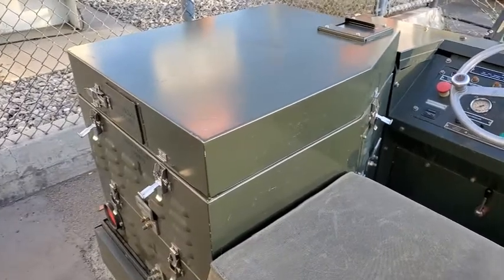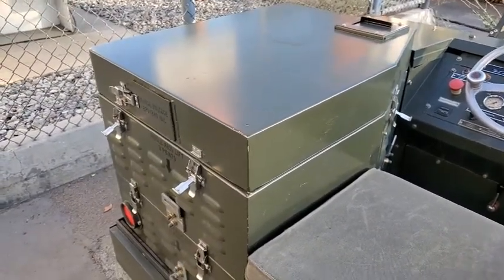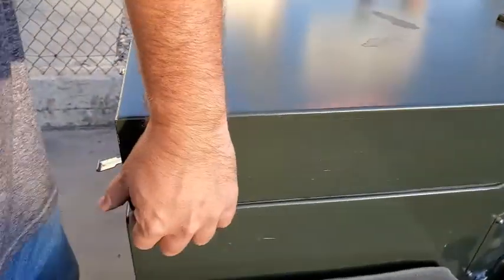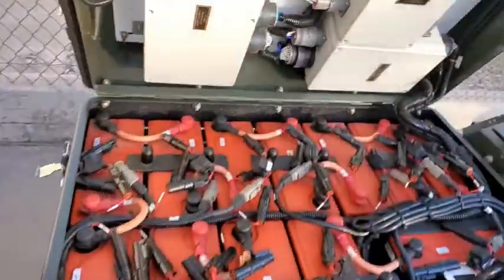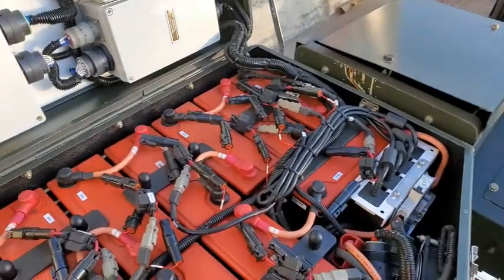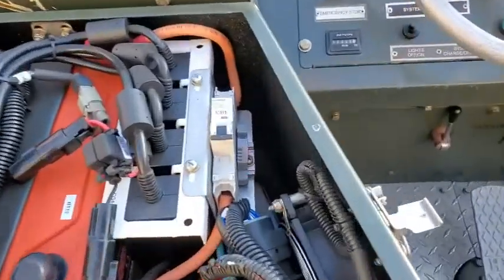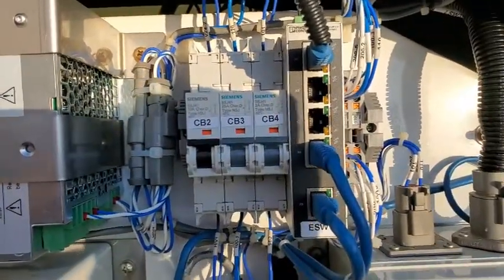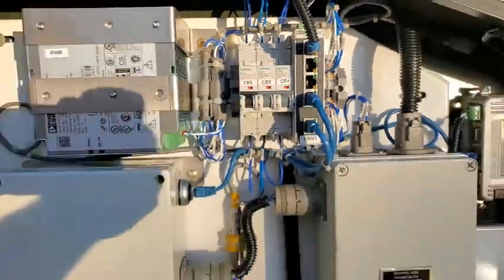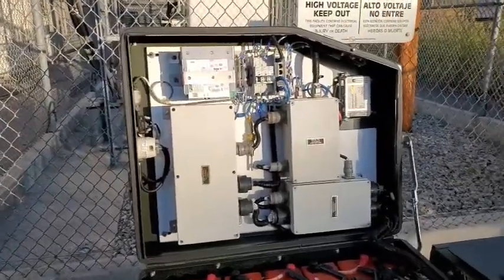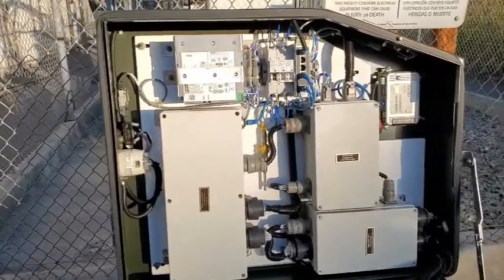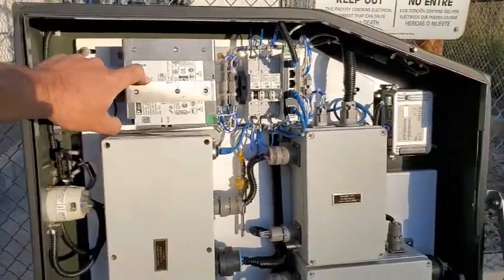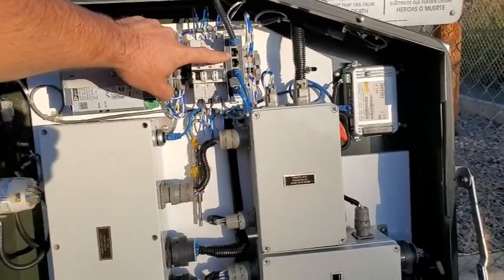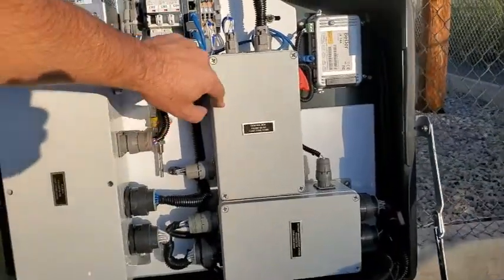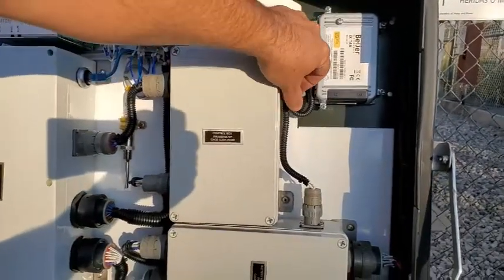Next, you want to disconnect these 3 latches, as you can see already, to get to the inside of your battery pack and make sure your circuit breakers are on and unit's ready for operation. So once you're inside, you want to check CB1 is on, CB2, 3, and 4 are on. Inside the top cover of your battery pack, you'll find your power supply, circuit breakers, Ethernet switch, control box, which on the side has the emergency charge switch.